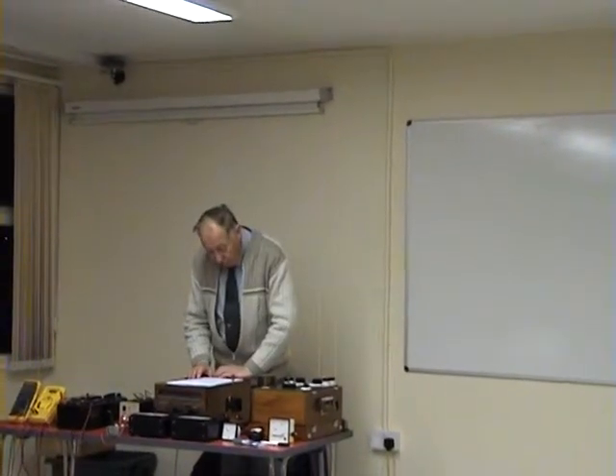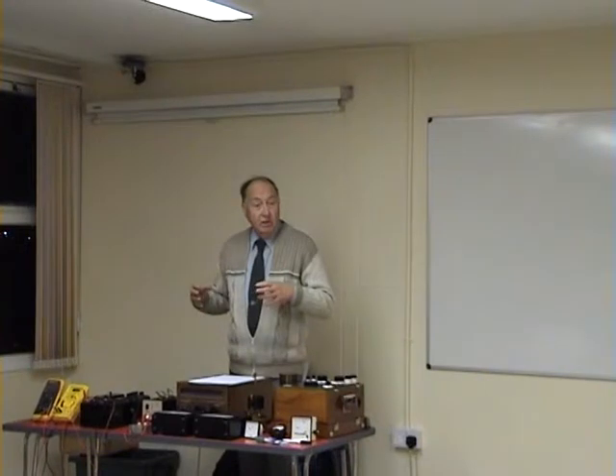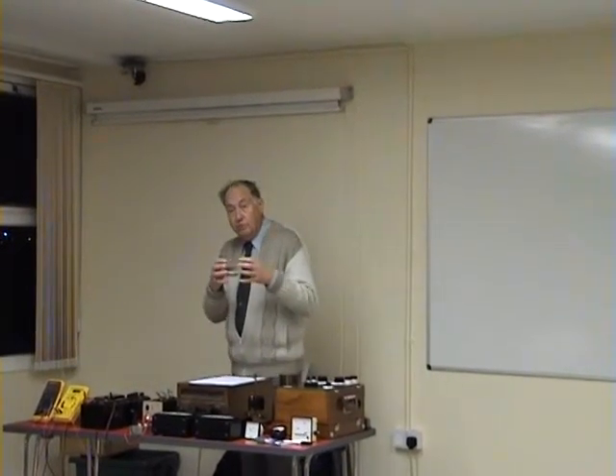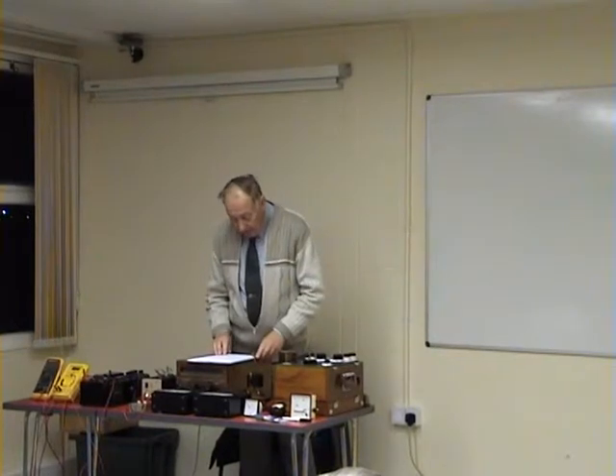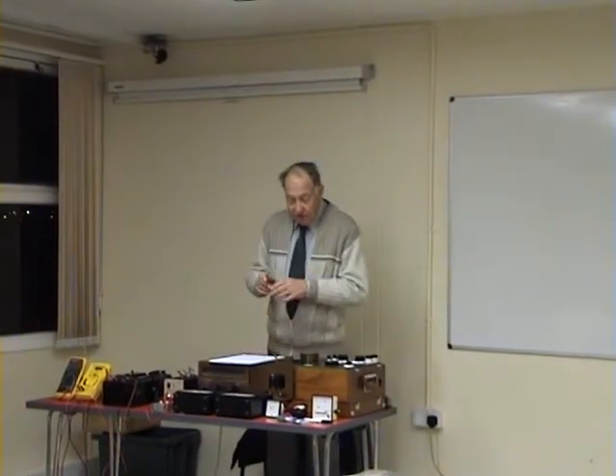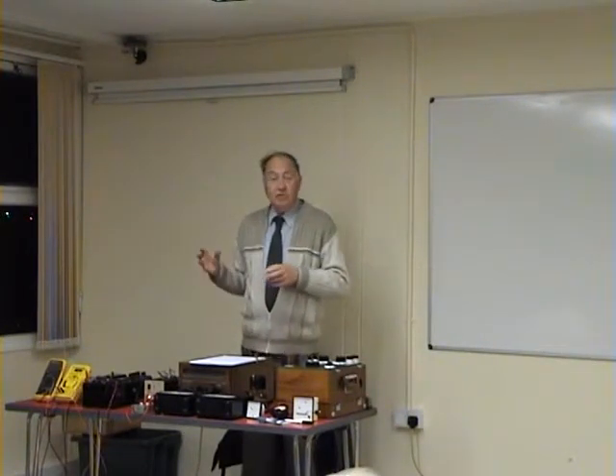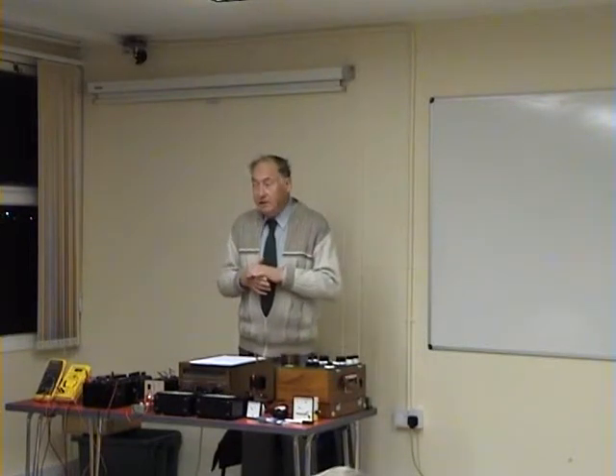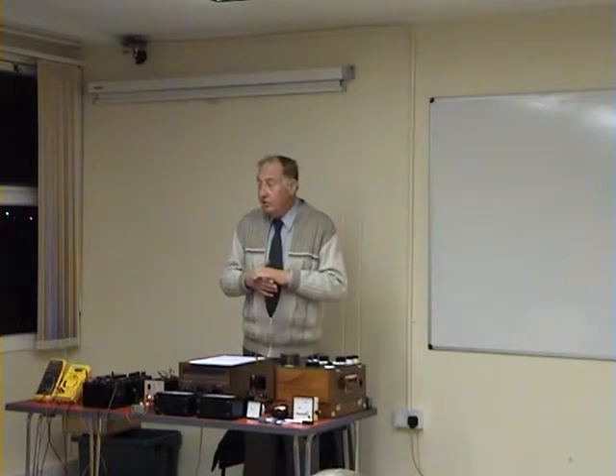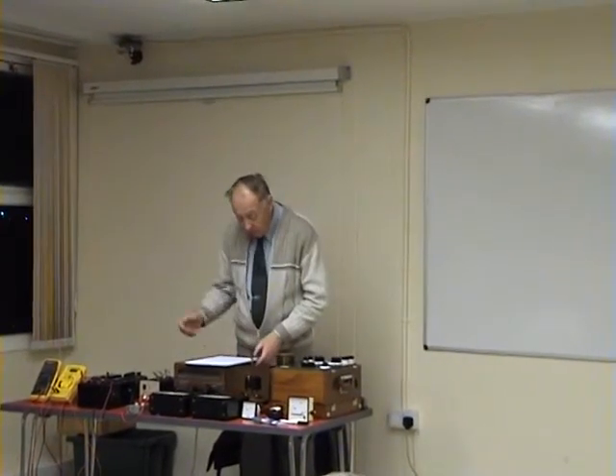There are two means by which they work. The first is a solenoid wound with a piece of iron inside it. As the current increases, the solenoid pulls the iron further and further into it, and it's coupled to the meter needle of the scale. The other type has two separate iron vanes, one of which has a coil around it, and the two vanes are linked. As current flows through the one iron, the other vane also takes the same polarity. We know that like charges repel, so the vanes open up and show the indication on the meter.